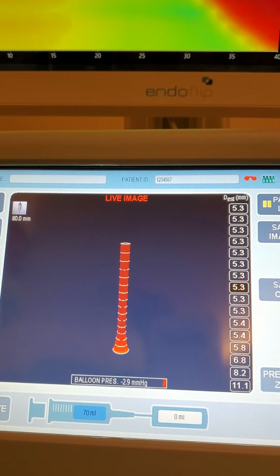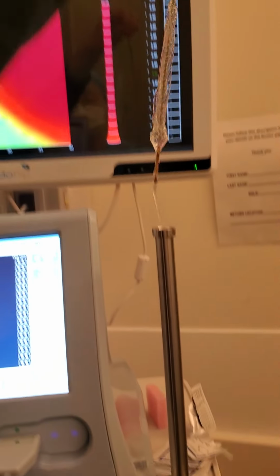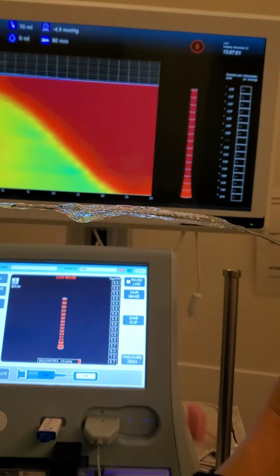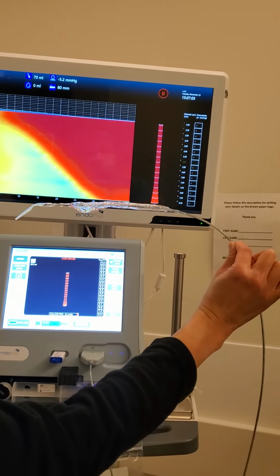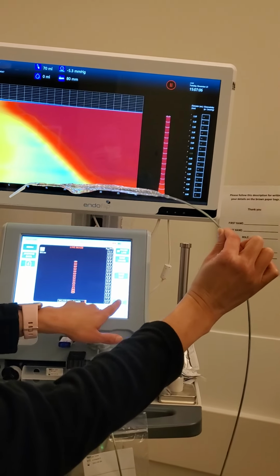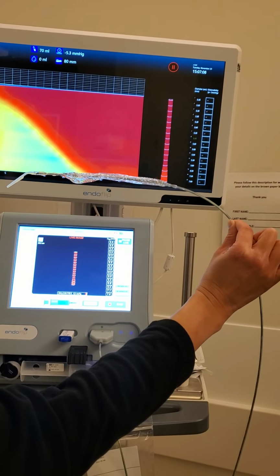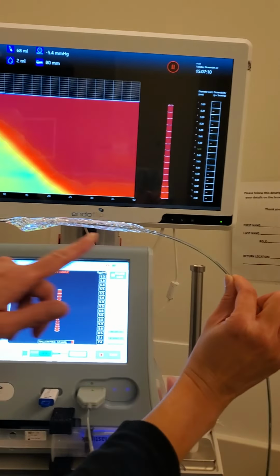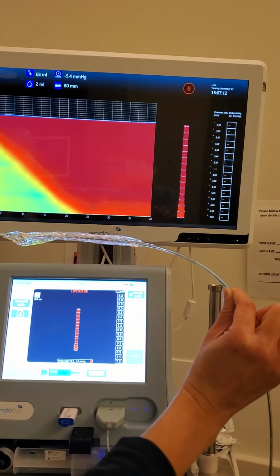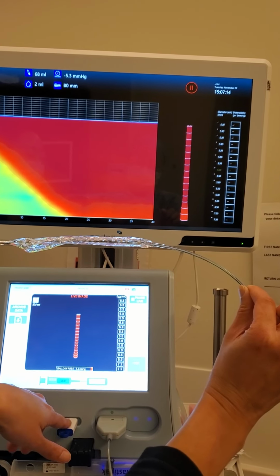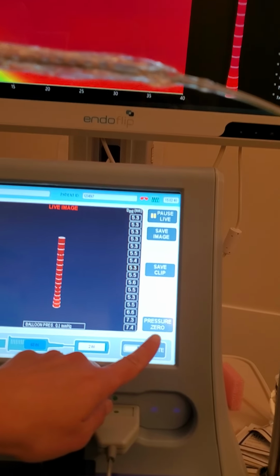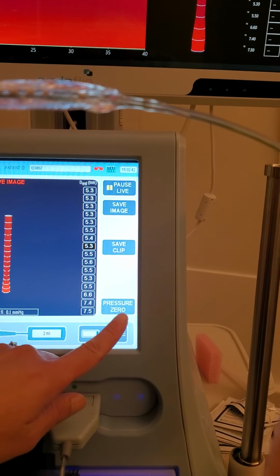It's like negative pressure. So before you use the balloon, you're going to hold the balloon horizontally in the air. Back up so you can see how I'm holding it. You're going to hold the balloon horizontally in the air without touching any of the sensors, and you're going to press this pressure 0 button. What it does is it zeroes out the pressure because there's always a little liquid left in the balloon. So it's going to zero out the pressure internally so that it can read accurately. You're going to watch this button, and when the pressure 0 button comes back like it just did, then you can go ahead and use it.